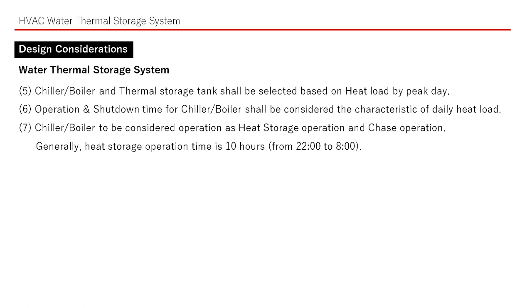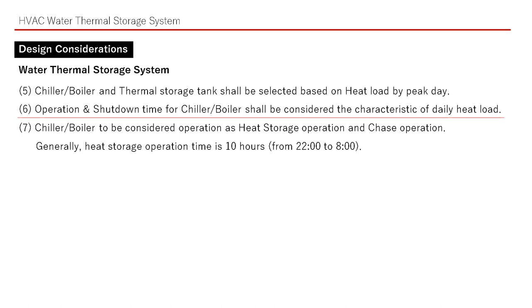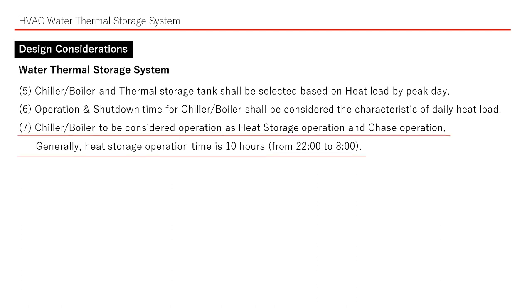We will read through the design considerations. The chiller, boiler, and thermal storage tank shall be selected based on heat load by peak day. Operation and shutdown time for chiller and boiler shall consider the characteristic of the daily heat load. The chiller and boiler shall be considered for operation in heat storage mode and chase operation mode. Generally, heat storage operation time is 10 hours, from 22:00 to 8:00.